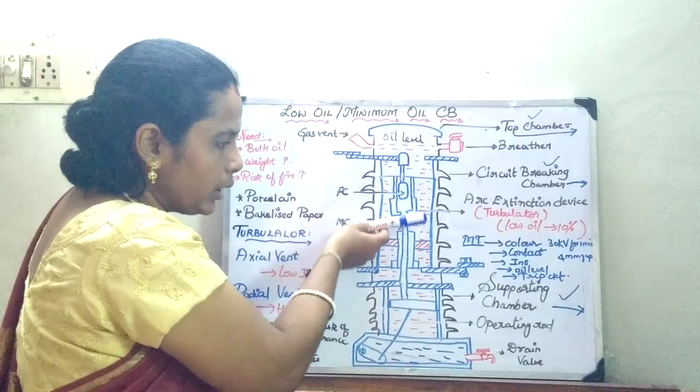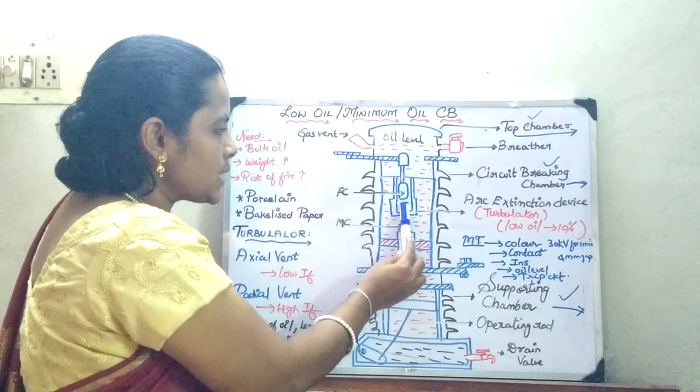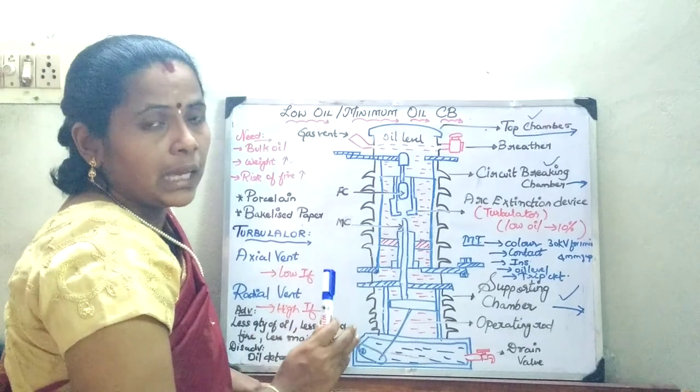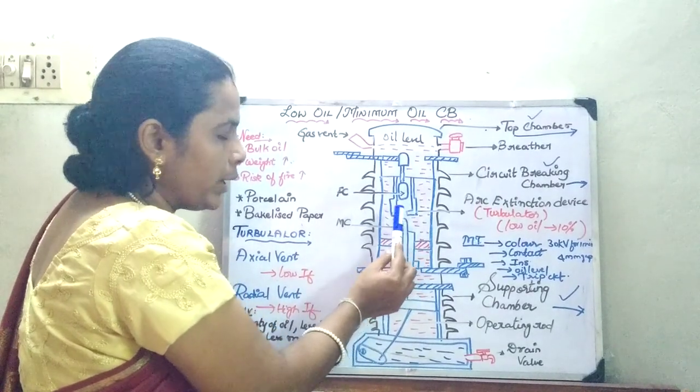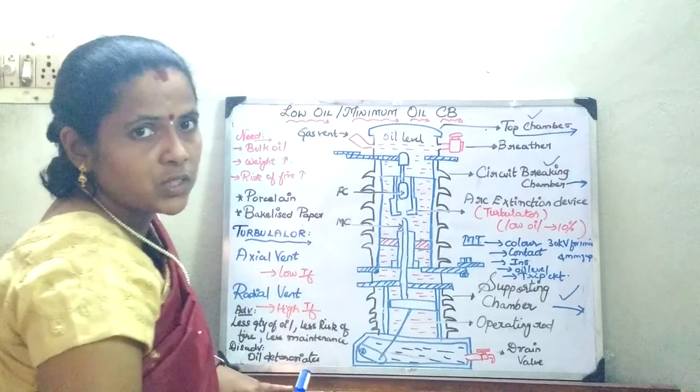As a result, this moving contact is going to be pulled down. In case of low fault current, this axial vent itself is sufficient enough to quench the arc. In case the fault is going to be higher, then you are going to have a radial vent also which forces the oil from all the sides to quench the arc.